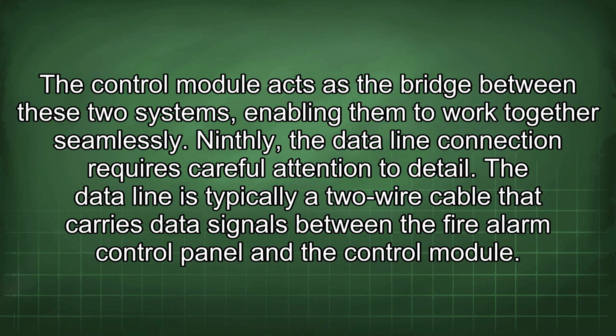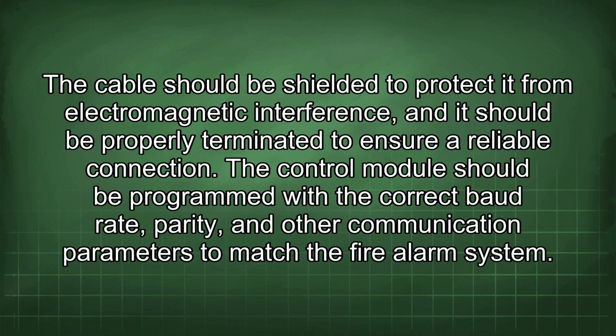Ninthly, the data line connection requires careful attention to detail. The data line is typically a two-wire cable that carries data signals between the fire alarm control panel and the control module. The cable should be shielded to protect it from electromagnetic interference, and it should be properly terminated to ensure a reliable connection. The control module should be programmed with the correct baud rate, parity, and other communication parameters to match the fire alarm system.